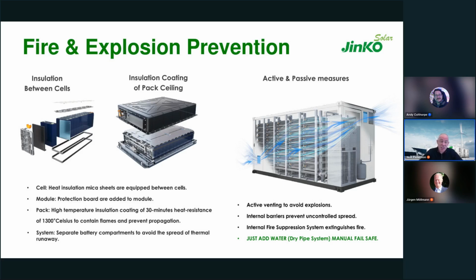electronics at the module level. We have electronics at the cell level. There's the 30-minute heat resistance coating on the inside of the module itself. That provides up to 1300 degrees Celsius, which prevents propagation of what we call a thermal event, an exothermal event from the cells. That stops that propagating outside, and it's the propagation of any exothermal event that we look to prevent when we do all of these certifications. Your 9540A, your IEC 62619, there's different variants of those in different countries as well. So we look to mitigate against the propagation of heat and of fire flames.